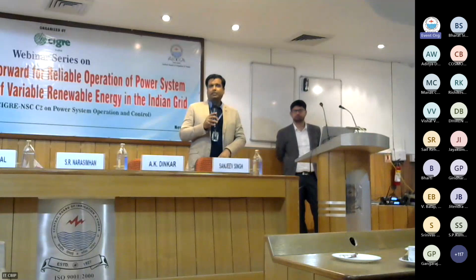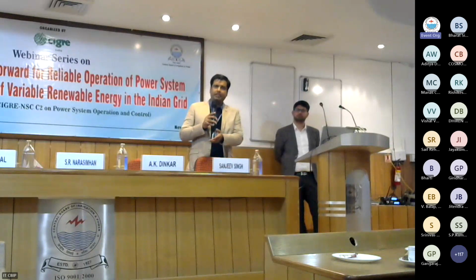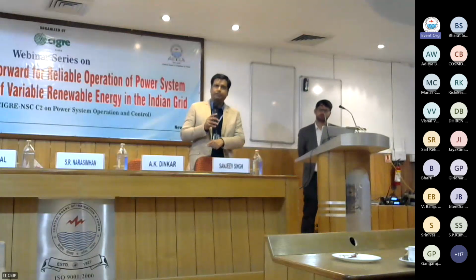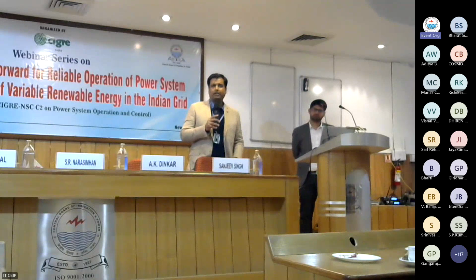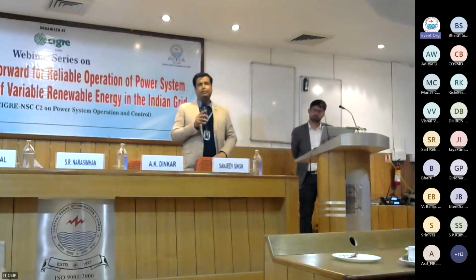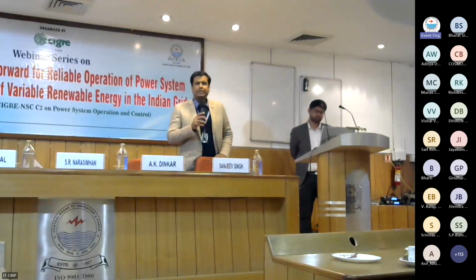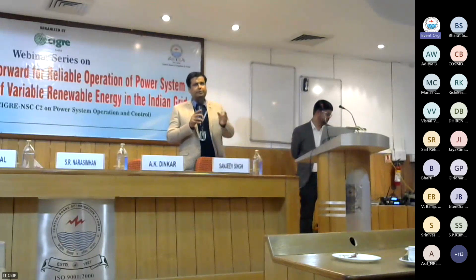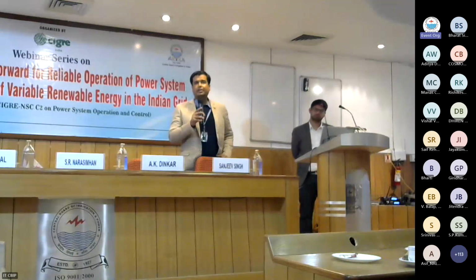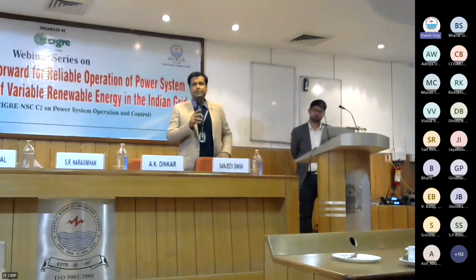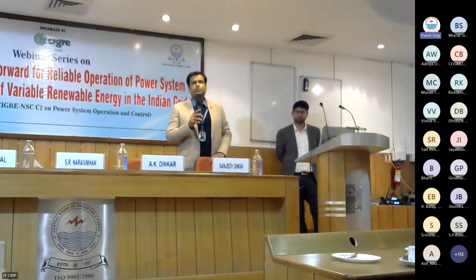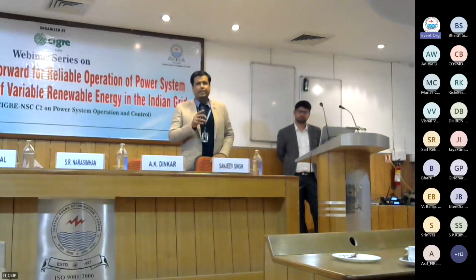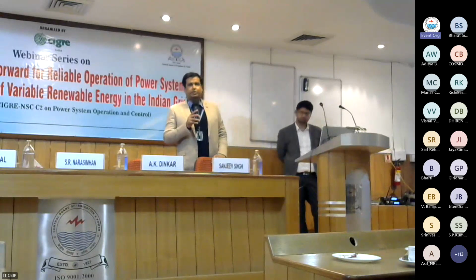IEEE 519 is to be followed by... 519 is very old. No, it has been updated. They had revised it. It is 2022. The latest version is 2022, and the plants have to follow IEEE 519 2022. And those details are very elaborated. And apart from that, 2022 gives an indirect reference to IEEE standard 2800 also for measuring of power plant harmonics. So I feel those are very clear, and 519 is mentioned in the CEA regulation.